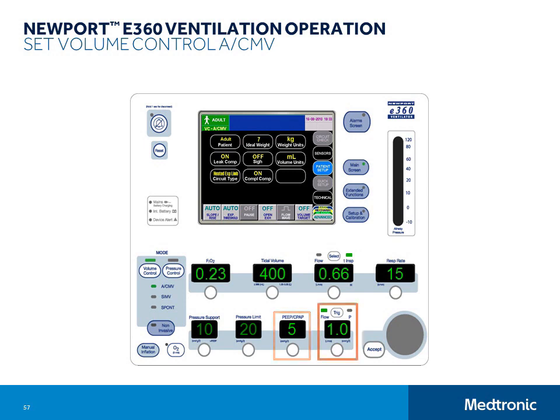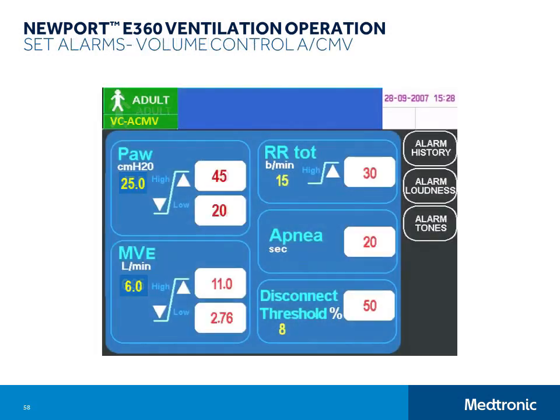Now let's set the alarm limits. We won't cover the alarm setting function for each mode and breath type, but let's go over it just this once. Touch the alarm screen button to open the alarm screen. While ventilating, the monitored value for peak airway pressure, expiratory minute volume, total respiratory rate, and percent VTE variance are shown just to the left of the alarm settings so that you have a point of reference. When setting alarm limits before you start ventilating, just pick safe values first. Then go back and tailor them to match your individual situation after you start ventilating the patient.